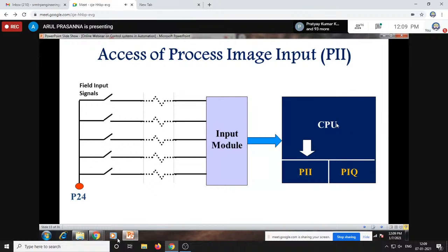Then the CPU comes back to the PIQ, and if some output is going to get turned on for that input, it updates the PIQ chart, meaning the CPU commands a particular byte or bit value to change from 0 to 1. Once that bit value is changed, it is reflected as 5 volts in the output module, which converts that 5 volt back to 24 volts for the field output device. This is the complete cycle happening inside a PLC.